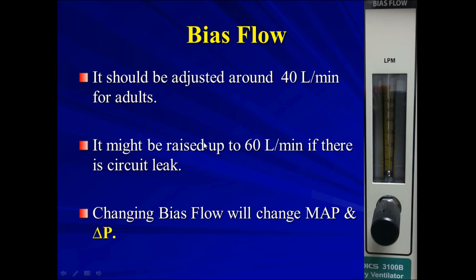We can increase the bias flow up to 60 liters per minute if there is a circuit leak. Changing bias flow will change the mean airway pressure and the delta pressure. So whenever you do any change in this machine, you have to check the other settings. If you change the mean airway pressure, it might affect all of the settings like the delta pressure. Same for the bias flow — if you change it, you affect the mean airway pressure and the delta pressure.